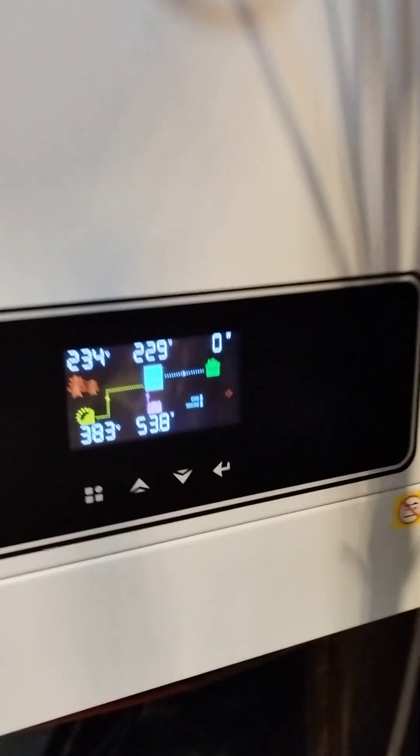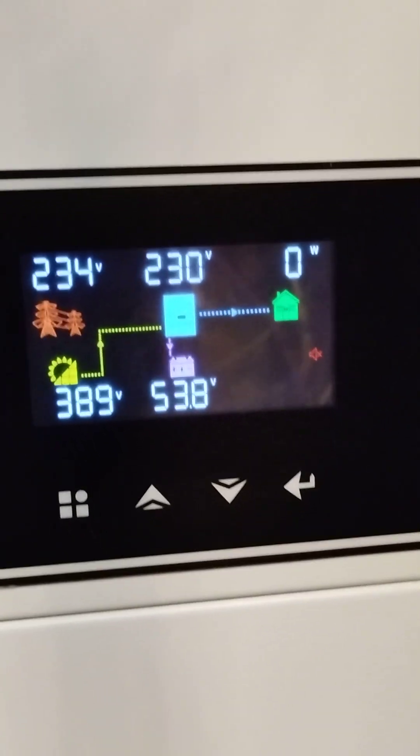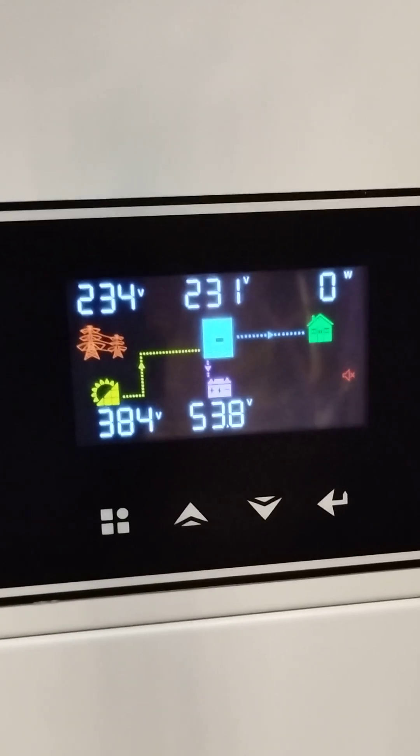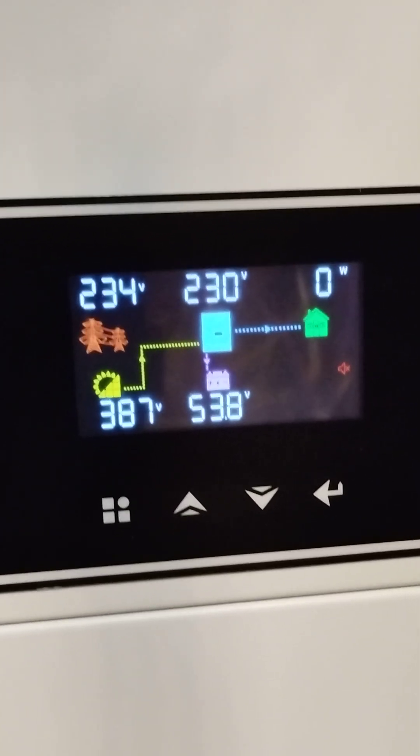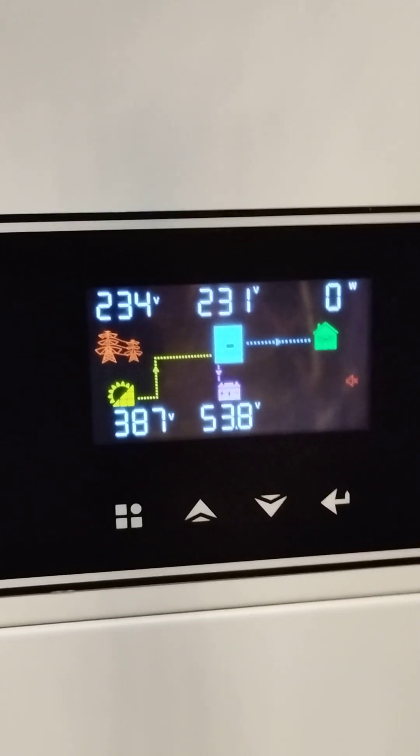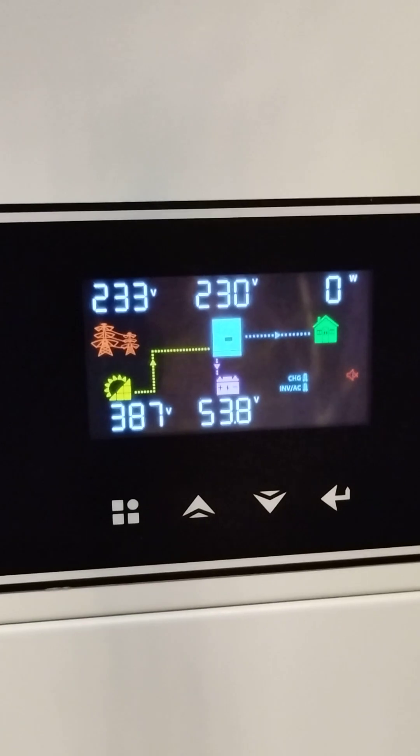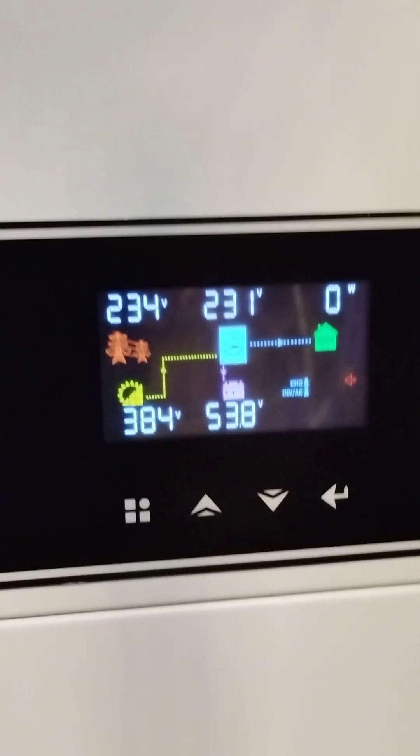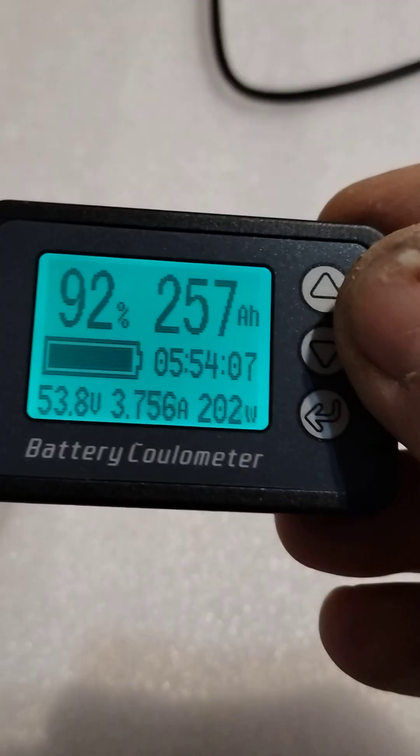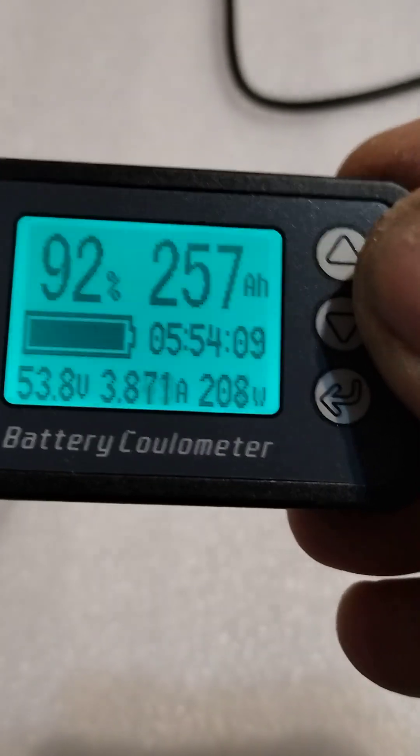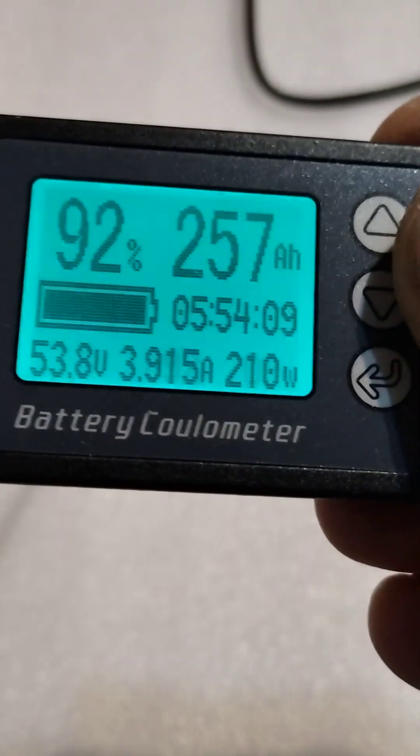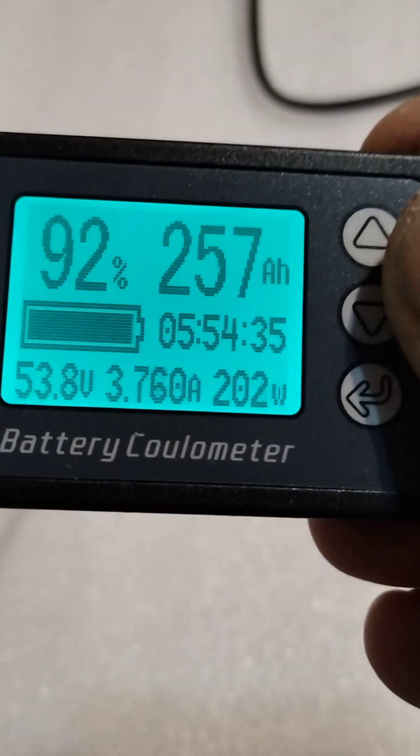And we are looking at a very good MPPT performance, about 384 volts MPPT voltage out of 430 volts open circuit, and let's see the power being fed into the batteries, about 208 watts, 210 watts.